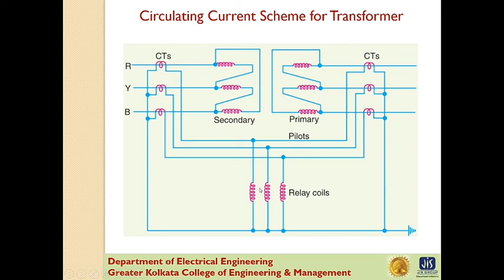Next is the problem. A three-phase transformer of 220 by 11,000 line volt is connected in star delta. The protective transformer on the 220 volt side has a current ratio 600 by 5. What would be the CT ratio on the 11,000 volt side? Now, the line current on the 220 volt side is 600. So the phase current of the delta connected CTs on the 220 volt side is equal to 5 ampere because the ratio is 600 by 5.